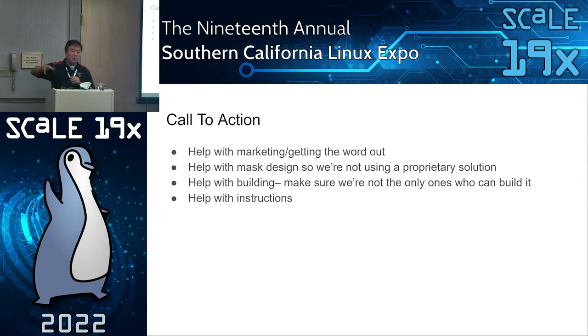Well, the FDA doesn't actually regulate that space. NIOSH regulates the space. The reason you want NIOSH approval is because if you want to sell it commercially and you want it to be used in regulated spaces, NIOSH is closely associated with OSHA. If you're in a field that requires the usage of a PAPR, it has to be certified by NIOSH, otherwise you're not covered under the protection of your employees, and therefore there are liability issues. So if you're going to be using it in a commercial venture or employment as a protective measure, it's not going to happen with an open source device in the current regulatory environment.